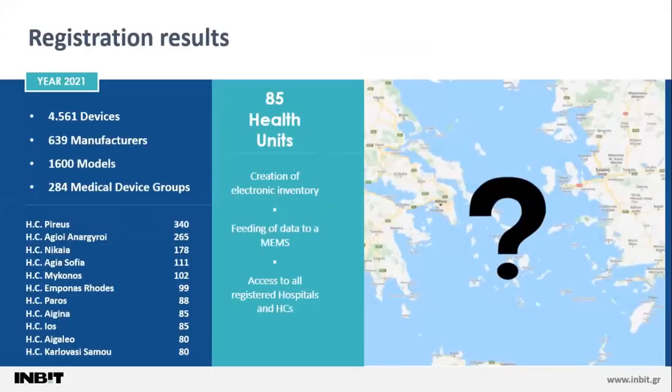The results of the registration were that 85 health units were registered, an electronic inventory was created, data were fed to a MEMS, and access was given to all hospitals and health centers. The numbers show that over 4,500 devices were registered, from about 640 manufacturers, belonging to 1,600 models, and categorized across over 280 medical device groups.